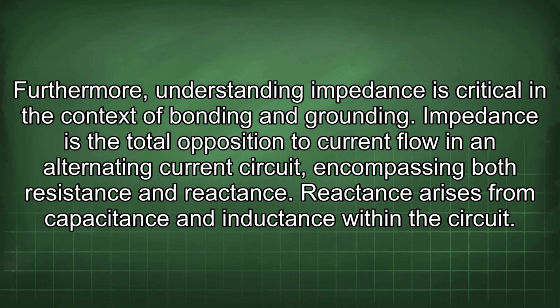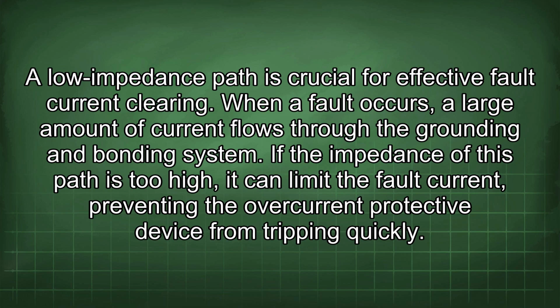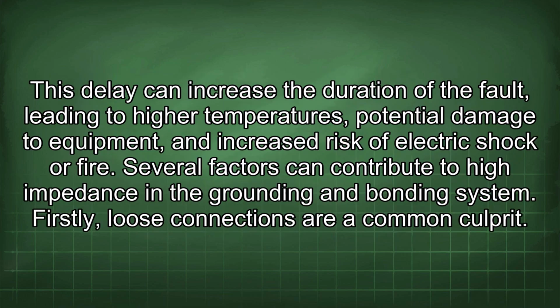Impedance is the total opposition to current flow in an alternating current circuit, encompassing both resistance and reactance. Reactance arises from capacitance and inductance within the circuit. A low impedance path is crucial for effective fault current clearing. When a fault occurs, a large amount of current flows through the grounding and bonding system. If the impedance of this path is too high, it can limit the fault current, preventing the overcurrent protective device from tripping quickly. This delay can increase the duration of the fault, leading to higher temperatures, potential damage to equipment, and increased risk of electric shock or fire.